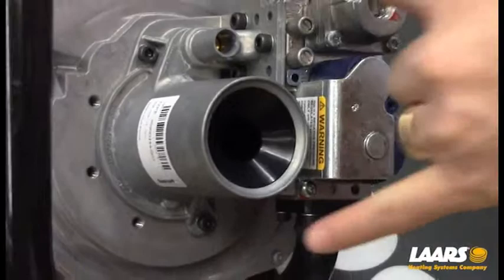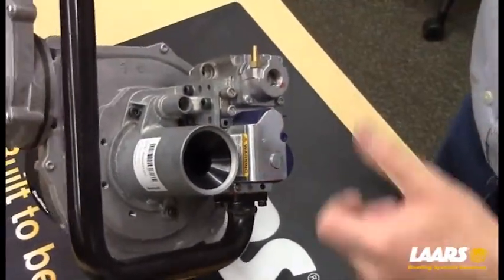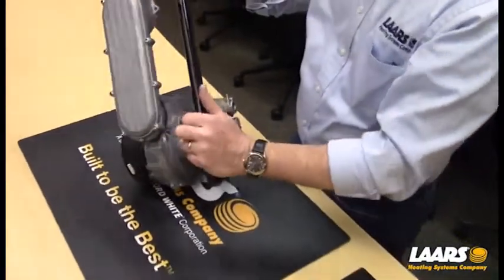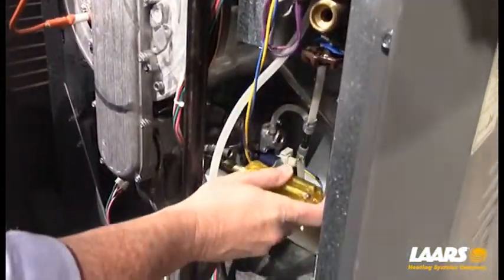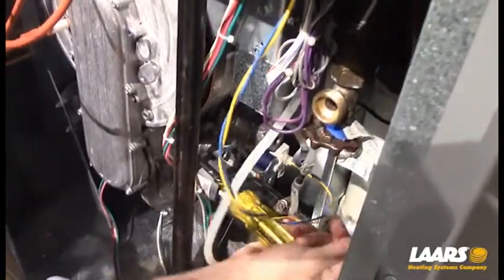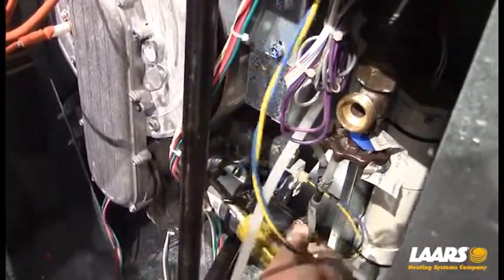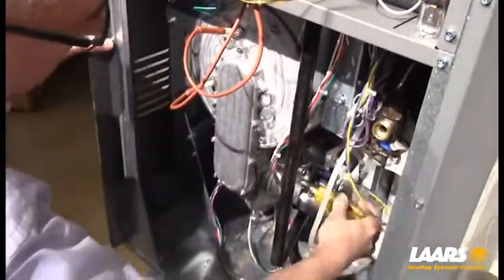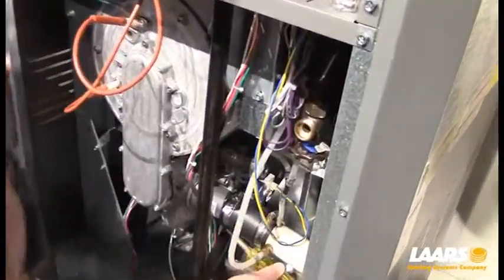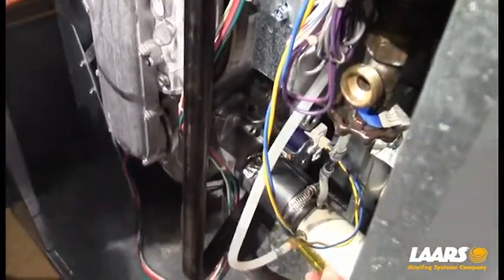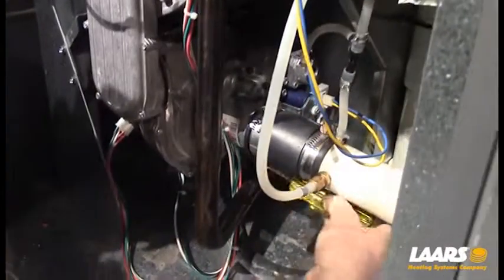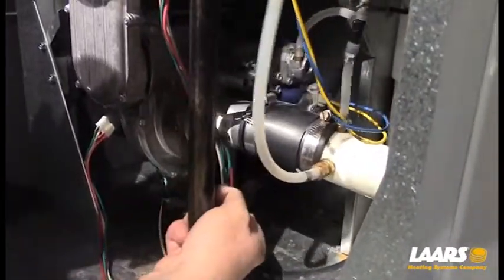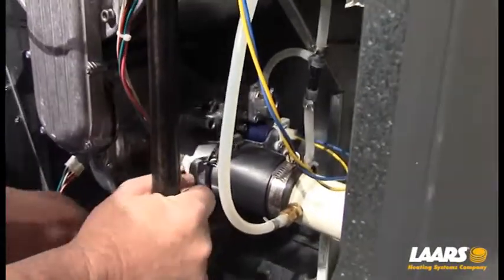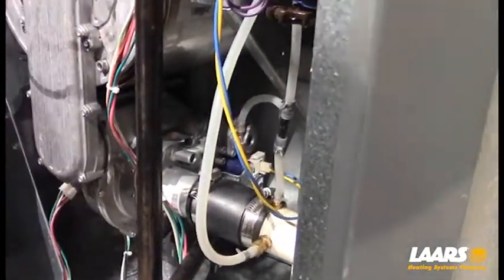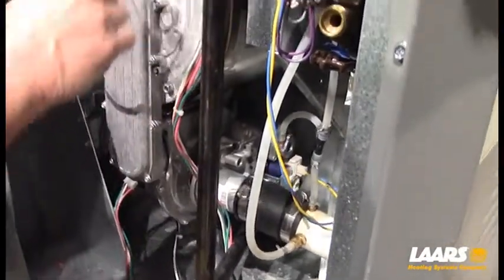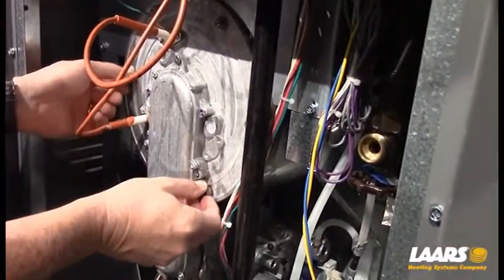So we're going to go back to the boiler. We're going to remove these 2 screws and the 6 number 10 nuts and take that whole blower, arm, and burner head out all as one piece. The first thing we're going to do is remove these 2 number 4 Allen screws that hold the venturi to the blower. Next, we're going to slide the arm or the venturi away from the blower itself. Now we have 6 number 10 nuts. We're going to take those off. I've already loosened those for us.